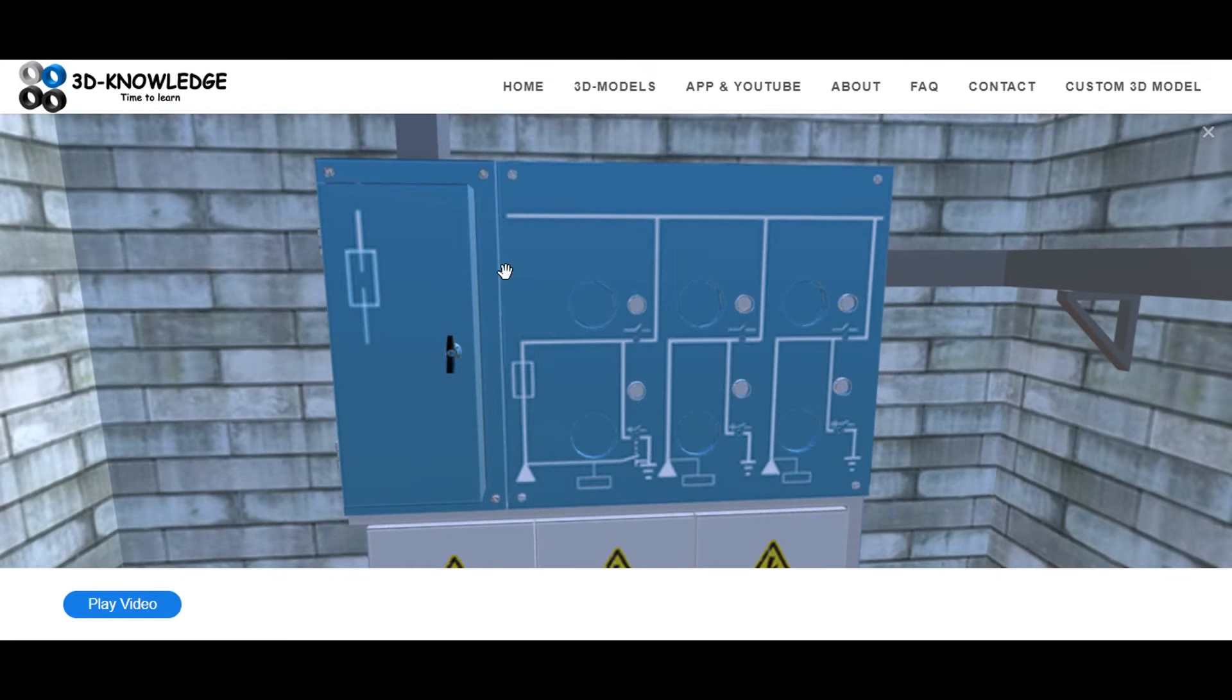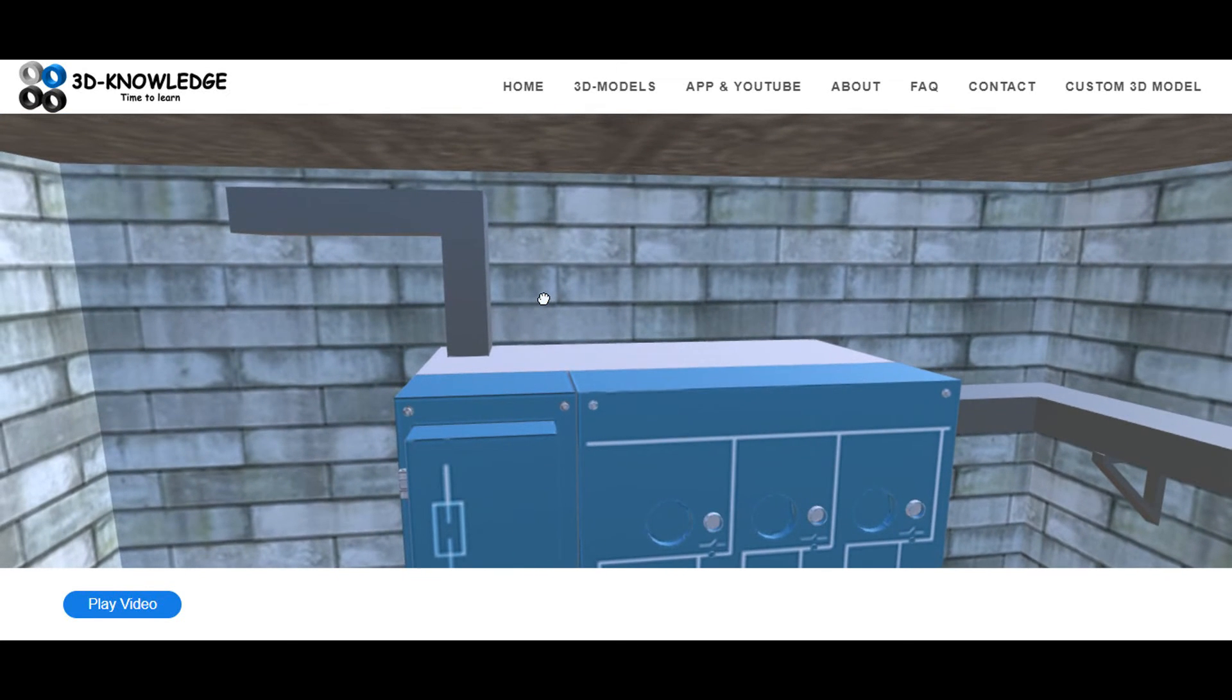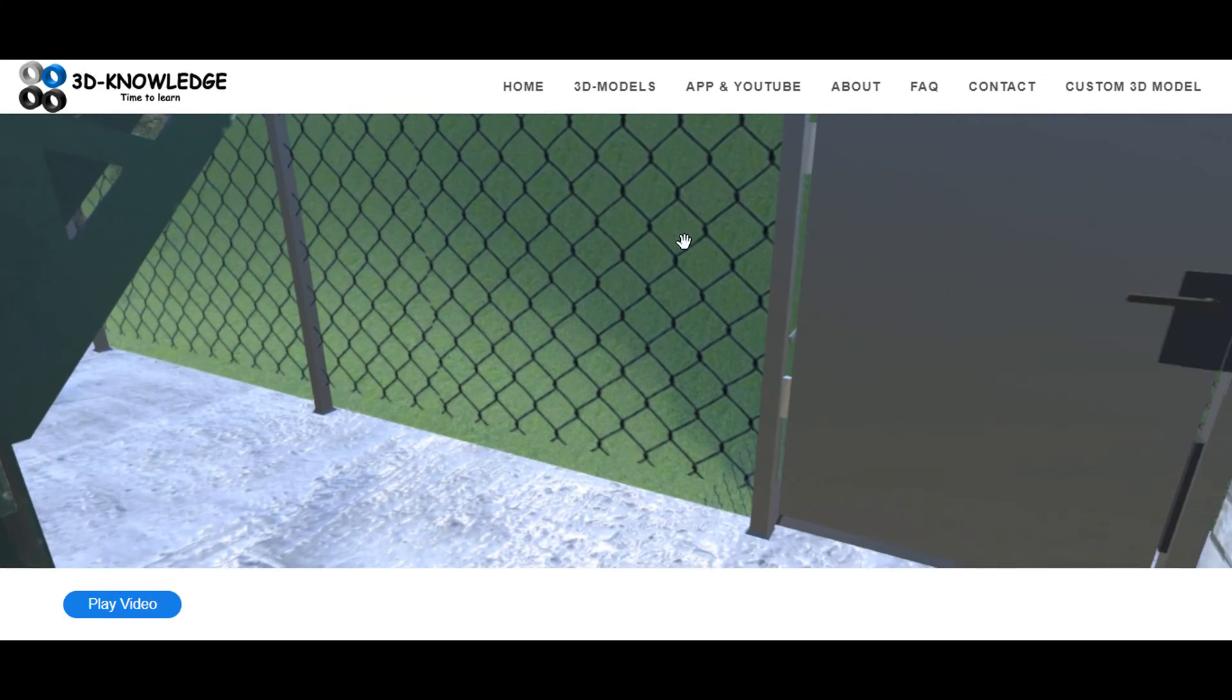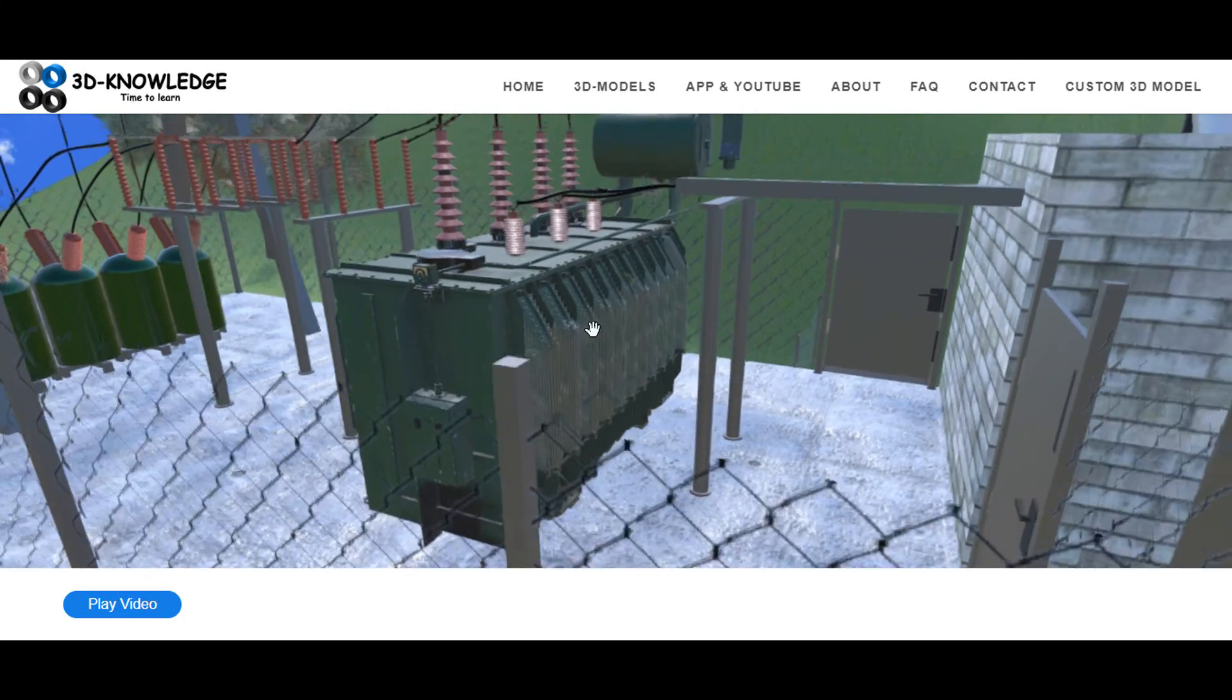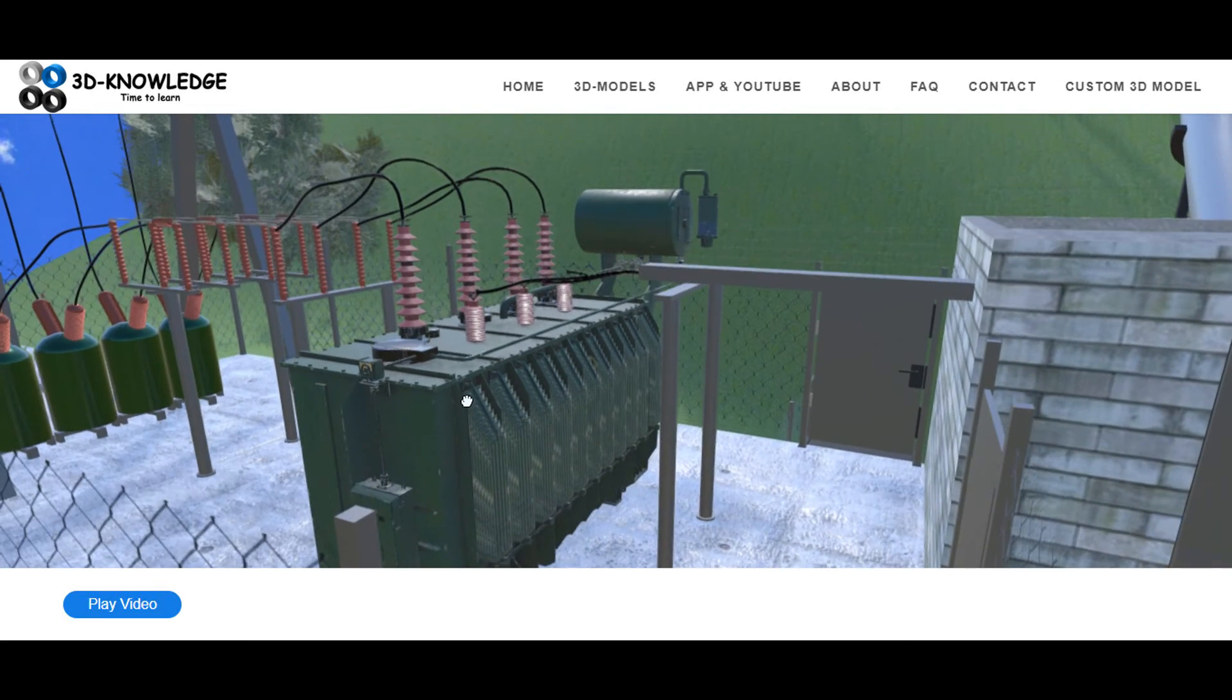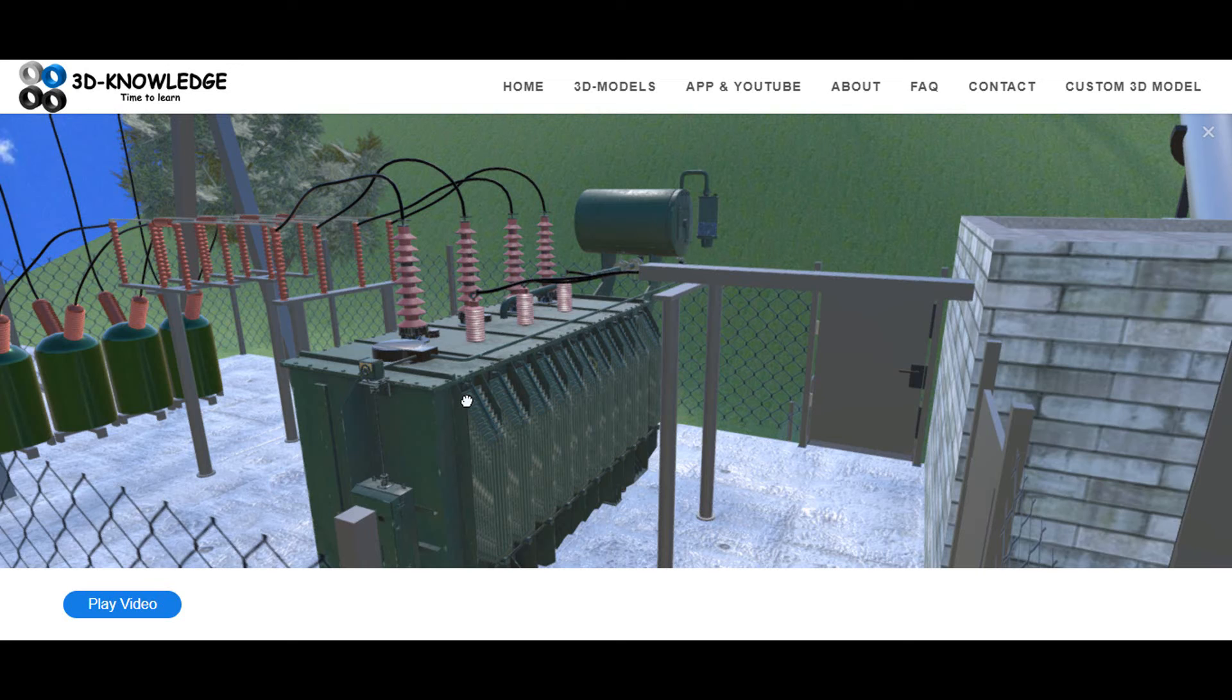Typical voltages here for the switchgear may be 10,000 volts or 6,000 volts, for example 6 kV, 10 kV, 20 kV. The type of switchgear used could be air insulated or vacuum insulated or maybe SF6. At some point we'll make a video on switchgear and I'll explain to you why we use different types of switchgear and for what purposes. The cabling connects to this green item which is a transformer. Now the green transformer is actually oil insulated or fluid insulated and it's going to increase the voltage, probably going to increase it to for example 110,000 volts. You need to increase the voltage because if you don't increase the voltage you're going to need huge cables to transfer that amount of power, so you step up the voltage in order to reduce the current.